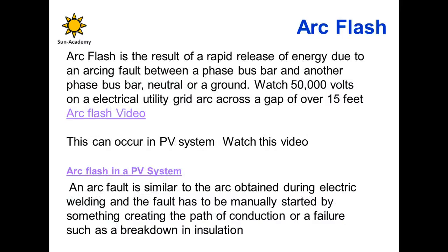What is arc flash? Arc flash is the result of a rapid release of energy due to an arc fault between a phase busbar and another phase busbar, neutral or ground. Watch 50,000 volts on the electrical utility grid arc across a gap of over 15 feet. Stop the video here and watch the following two videos, the arc flash video and the arc flash video in a PV system. An arc fault is similar to the arc obtained during electrical welding, and the fault has to be manually started by something creating the path of conduction or failure, such as a breakdown in insulation.